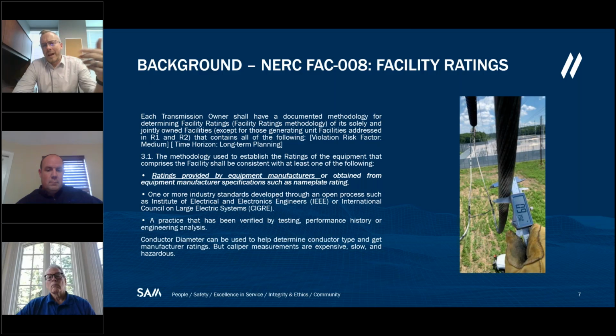You want to make sure that the amperage rating is correct, so that you don't inadvertently push too much current across that facility and overload the facility or a component in the facility, damage equipment, and trip the line off. That's where some of the blackout situations we've had over the past couple decades have occurred: you trip off a line due to undersized equipment, and bad things occur. The grid frequency gets off kilter and starts tripping generation offline, and it's a cascading effect. A big part of avoiding that scenario is to make sure your facilities are rated correctly.